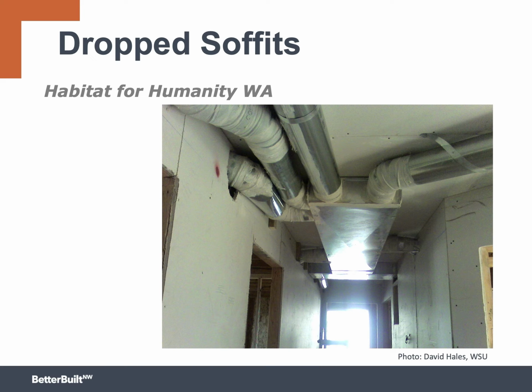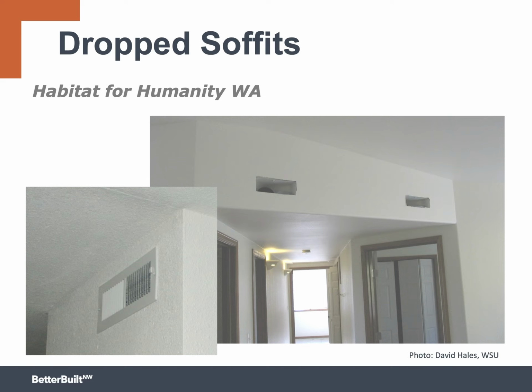Drywall was hung on all the ceilings and walls, and then the ducts were installed. You can see where they've punched through the drywall on the left side of the photograph here to get into a different part of the house. The framing for the soffit occurred after all the ducts were installed and sealed. The lower ceiling in the hall creates an architectural feature, a kind of visual interest. When you walk down the hall into the great room, it opens up into the larger space with a higher ceiling. Locating registers on interior walls is a good idea to shorten the duct runs. To get good air mixing, be sure to consult the Manual T grill selection.